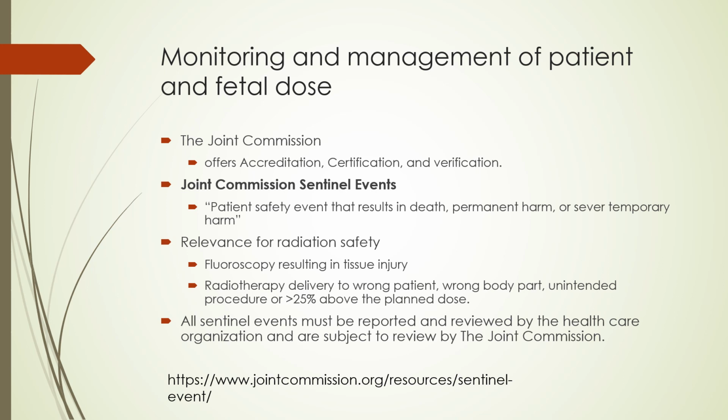The relevance of Joint Commission policies to radiation safety pertains to various ionizing radiations. The policy for fluoroscopy is that a sentinel event is any fluoroscopy procedure resulting in permanent tissue injury when clinical and technical optimization were not implemented and/or recognized practice parameters were not followed. For radiation therapy, a sentinel event is any delivery of radiotherapy to the wrong patient, wrong body region, unintended procedure, or greater than 25% above the planned radiotherapy dose. All sentinel events must be reviewed by the healthcare organization and are subject to review by the Joint Commission.